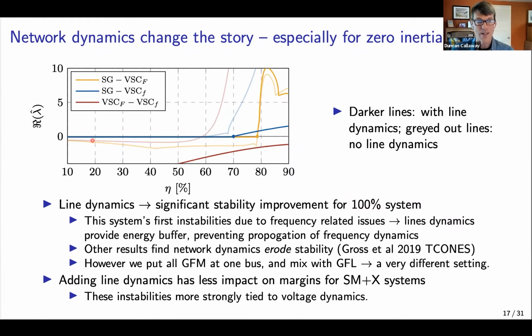Where the big difference comes in, which I haven't shown you yet, is when you have only grid forming and grid following converters, no synchronous machine. Here, penetration means how much of the system is grid following, starting from 100% grid forming and adding grid following at the alternate bus. Without network dynamics, the system becomes unstable at about 60% penetration of grid following converters. With network dynamics, we see no emergence of that instability.